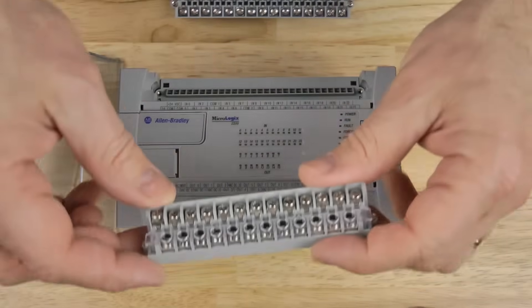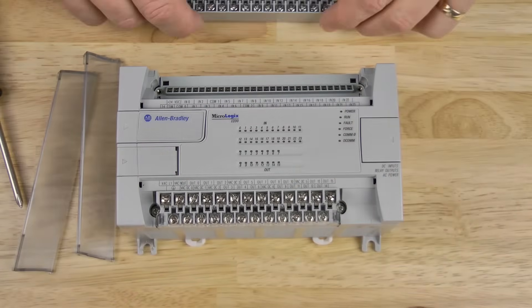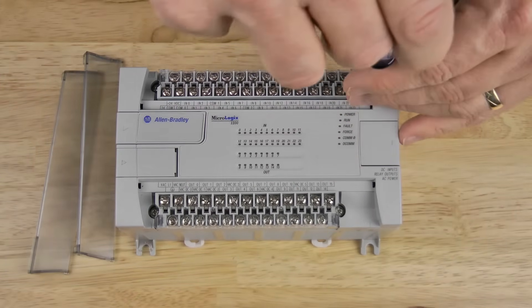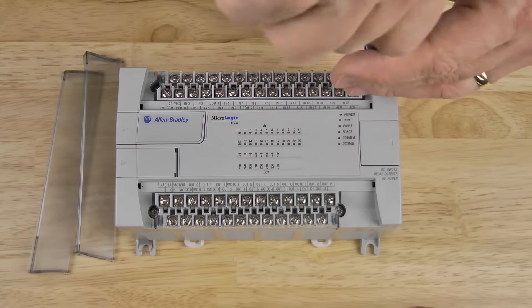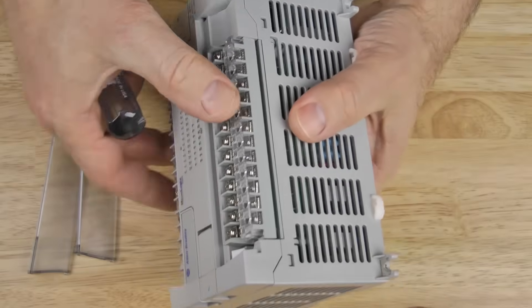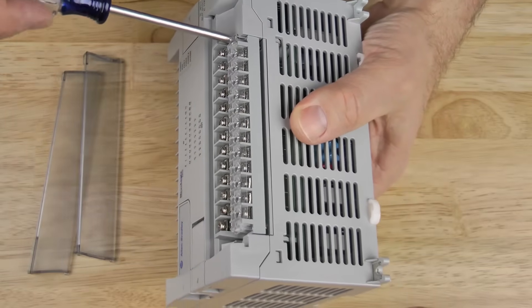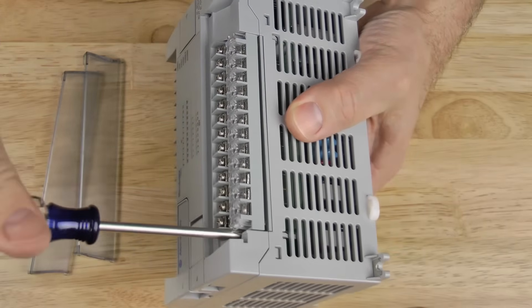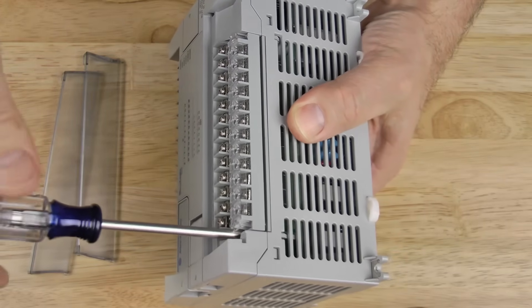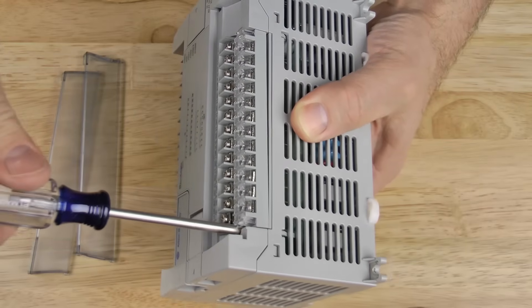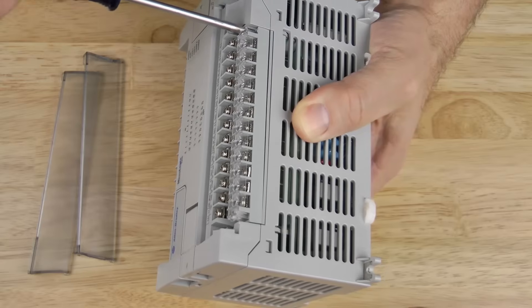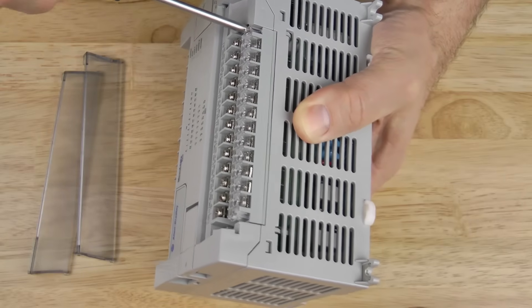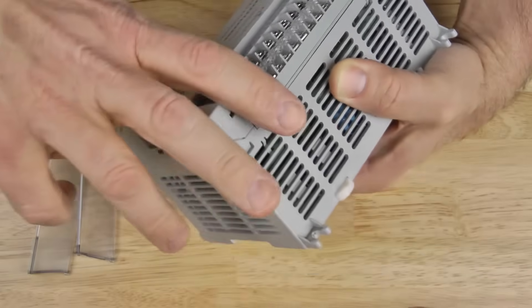Let's go ahead and reinstall these terminal blocks. Now one tip I will say when you're putting these in, put the first side in only halfway. Then screw in the second side. And then finish off the first side. If you try to put the first side in all the way, the terminal block will be at such an angle, it's very hard to get the second side in.